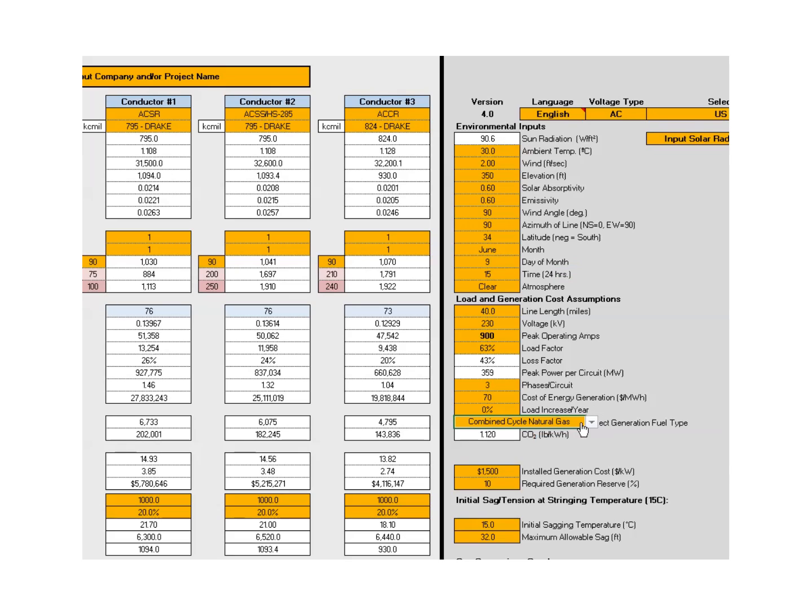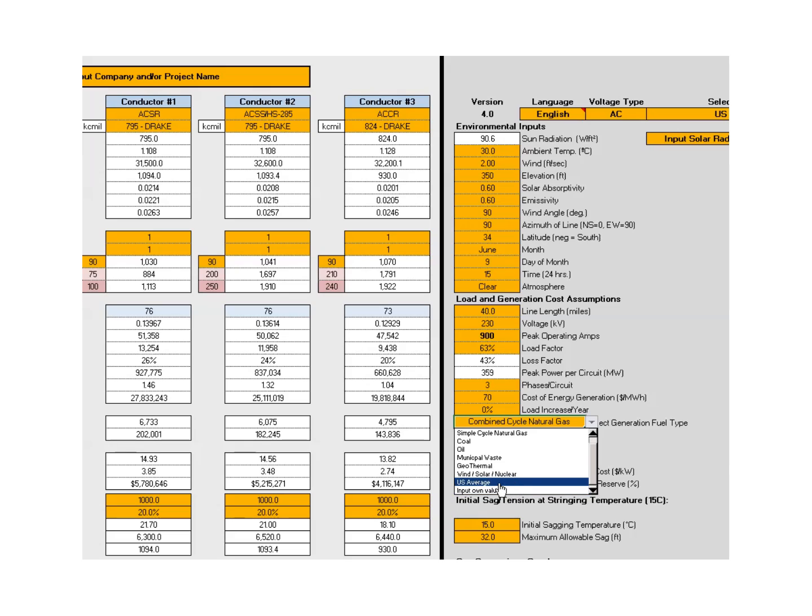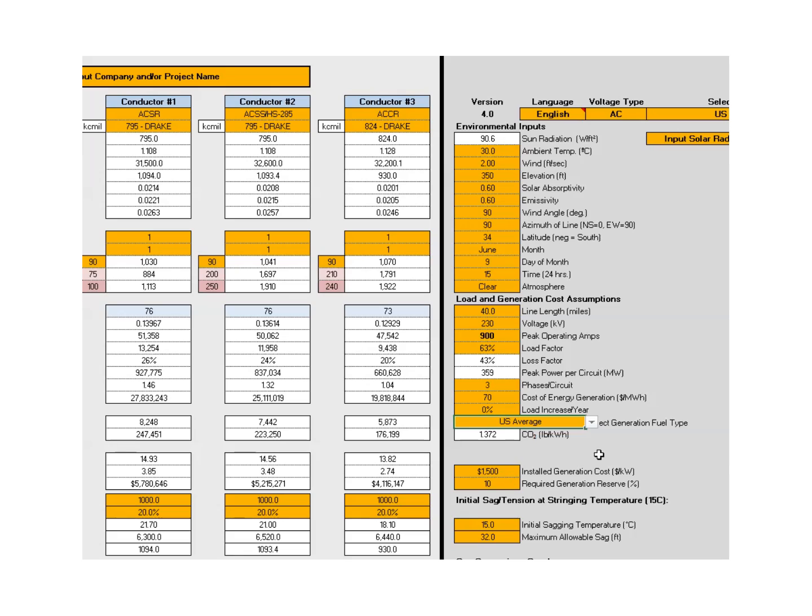We have the option, in terms of generation type, we can select from combined cycle natural gas, simple cycle natural gas, coal, oil, muniwaste, geothermal, or wind, solar, nuclear. And today we're going to just pick the national average. Of course, you can input your own value if you happen to have a blend of your utilities generation. The national average currently in the U.S. is about 1.372 pounds of CO2 per kilowatt hour.